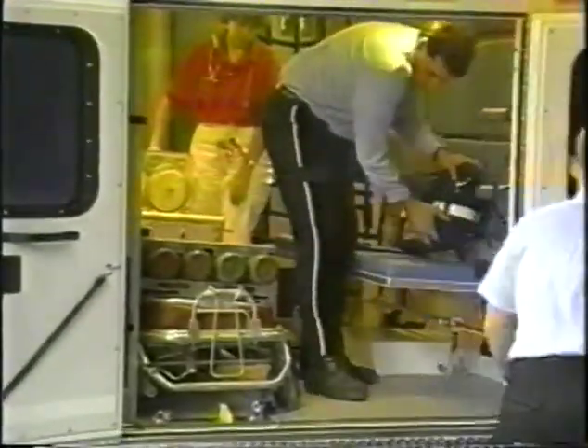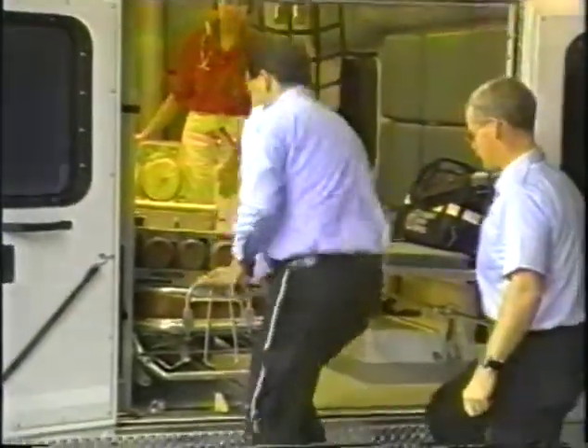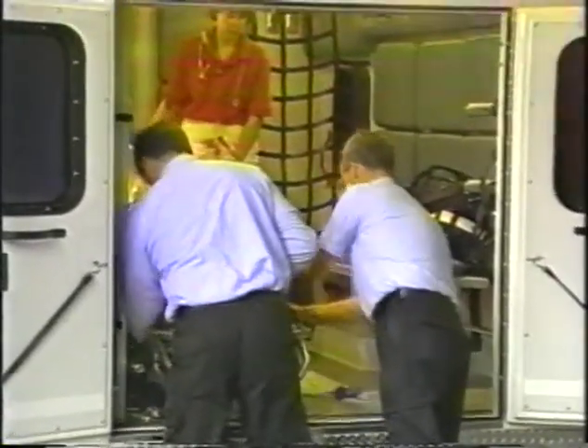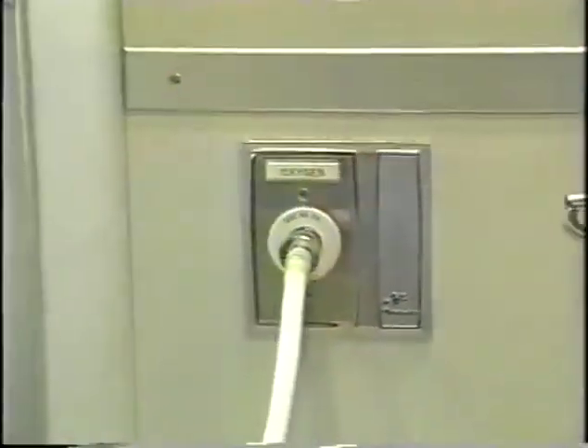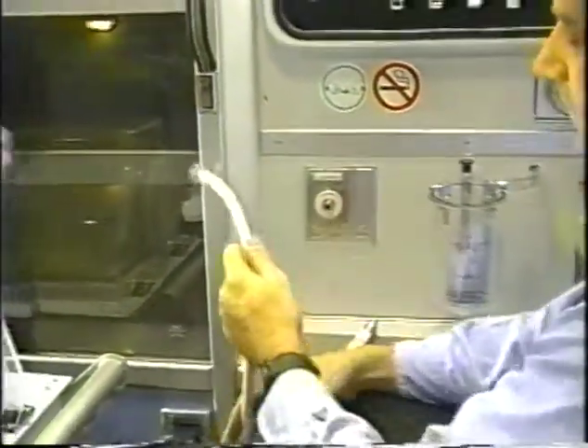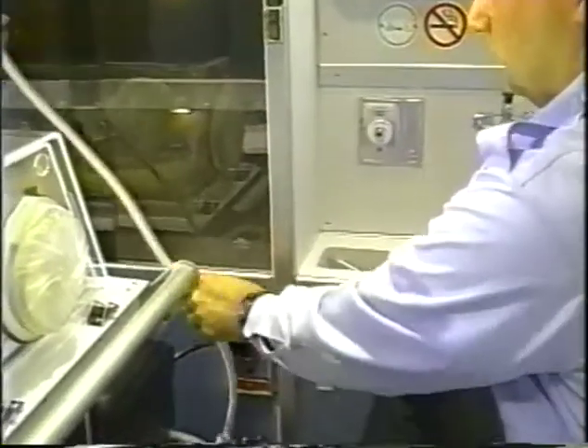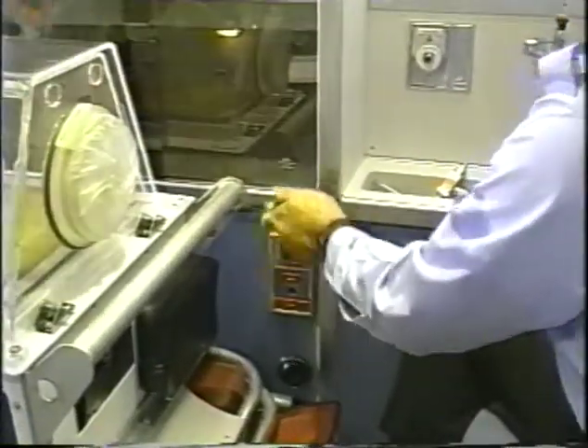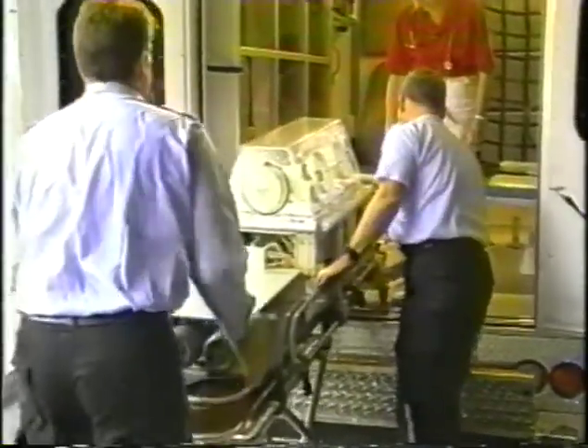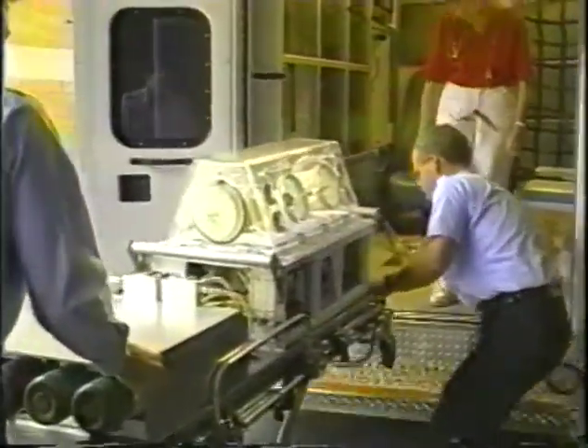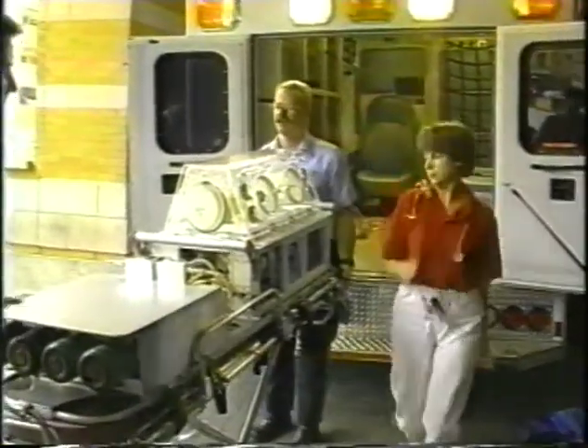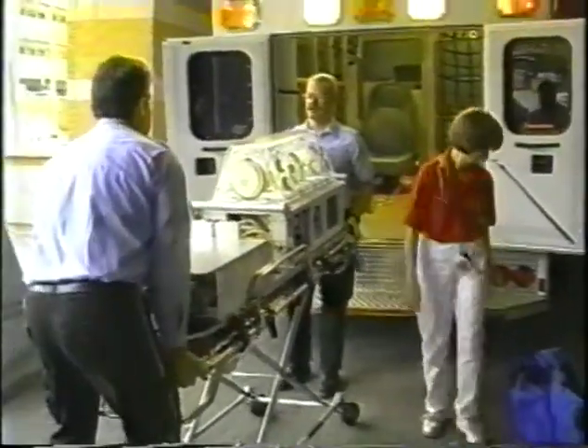Upon arrival at the destination hospital, remove the 2 supplemental restraint straps and place the straps back into the leg bag. Under direction from the accompanying medical staff, disconnect the oxygen from the onboard wall outlet. Also, unplug the 12-volt incubator plug and secure all cables and high-pressure tubing before unloading. Unload the 35A incubator combination in the usual manner. Lower the stretcher to level 5 or 6 if needed and move safely to the neonatal care unit.